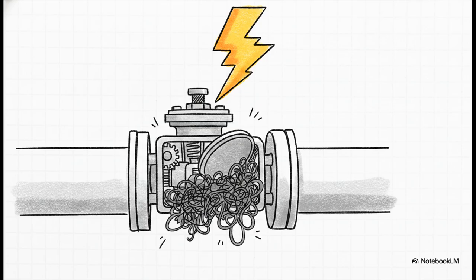Now, if all your safety circuits pass the power perfectly, but there is still no fire, you've reached the final gate, the gas valve itself. Your valve might be gunked up, mechanically stuck, or internally shorted out. It's getting the green light electronically for sure, but physically, it's failing to open the gas lines.